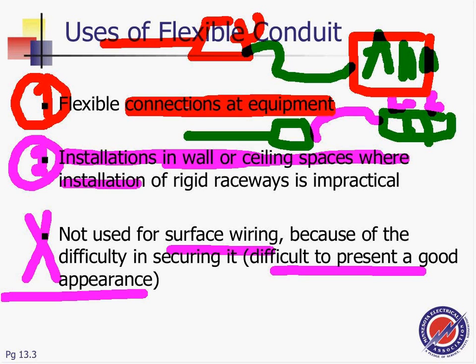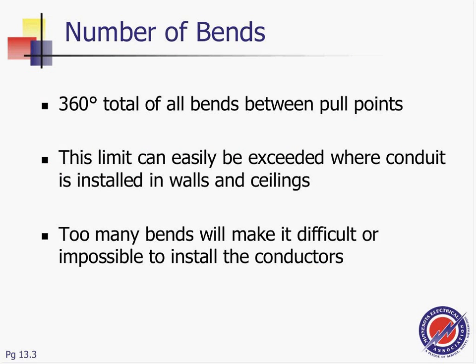What's the difference between fishing flex and fishing MC cable? MC cable is limited by the number of conductors it has, while with flex you can pull as many conductors in it as you need. So really, the question that always comes up is why can't they use an MC cable and call it a day, especially if I want to fish it in a wall. Well, what if you need to pull, say, 6 conductors? Are you going to custom design yourself a 6 conductor MC cable? It would be easier to pull a flexible metallic conduit in a drywall and just pull these 6 conductors into it, sized appropriately. So that's basically what is so common. Any question, guys? Any question about that? Seems a lot of you used it.